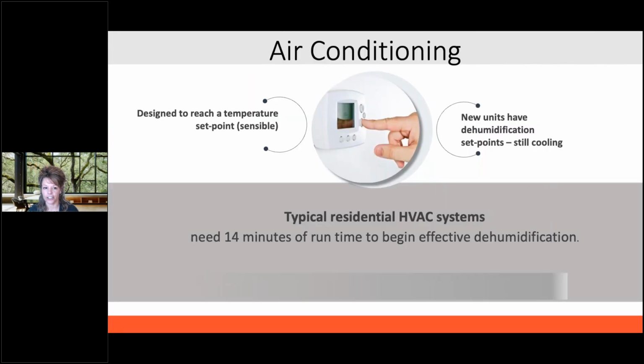So the air conditioner is designed to get to that set point. Yes, we've got dehumidification mode now, but most of the time it is still overcooling to dehumidify, and there has to be a load for it to be cooling. And you typically need about 14 minutes of runtime to get effective dehumidification, meaning that the coils have loaded and that water has started to drip down and out of the house.